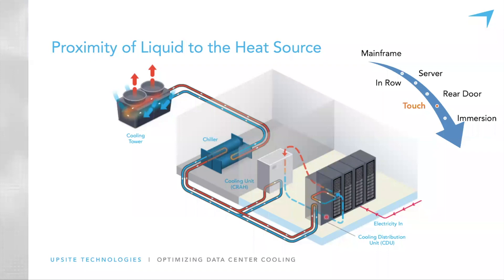We also still have a loop of air passing through the cabinets. This is for two reasons: there may be IT equipment that is not liquid cooled and requires air cooling, or the liquid-cooled device is not 100% liquid cooled — there's still a fan running, perhaps at only 20% of the speed it would run if purely air cooled, to keep some components cool that liquid cannot reach. This is a true hybrid situation with both an air loop and a liquid loop picking up heat from the source.